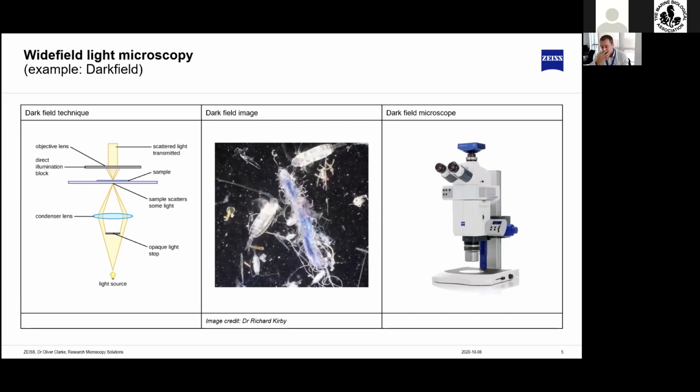And you have to make sure that you take a few things into account. You need a high dynamic range camera if you're going to get nice images. You also need to think about the vessel that you put the sample in. If you have something with lots of scratches and texture on the bottom of the dish, then you're going to also get interference. You won't get a nice black homogeneous background, which is what people look for in dark field imaging.